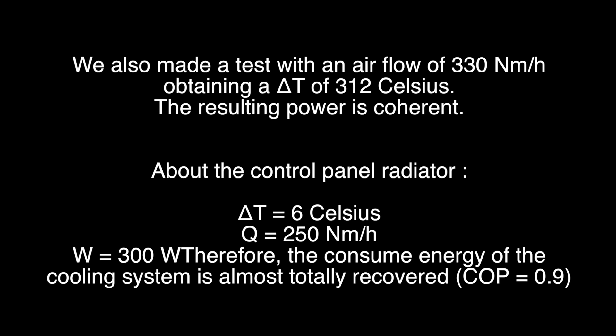Now, about the heat that is dissipated by the cooling system, it is recovered because, as you have seen, we get from the fan of 250 effective cubic meters per hour. We get using the same equation about 300 watts. We are consuming 380. So, the COP of the cooling system is about 0.9.